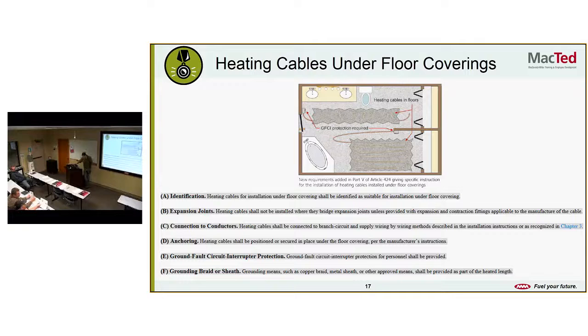So there's a new requirement added in Part 5 of Article 424 giving specific instruction for the installation of heating cables installed under floor coverings. There's identification. Heating cables for installation under floor coverings shall be identified as suitable for being installed under a floor covering. Expansion joints. Heating cables shall not be installed where they bridge expansion joints, unless provided with expansion and contraction fittings applicable to the manufacturer of the cable.